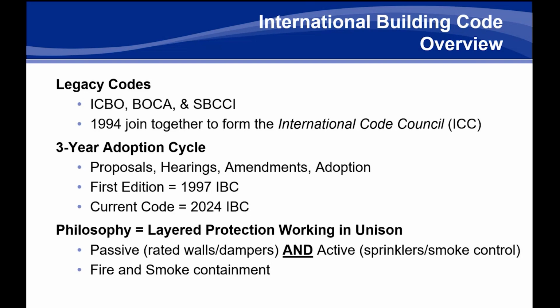The philosophy for that is actually a layered protection. So there's going to be a passive element and an active element. The passive element is typically you're going to be dampers or rated walls where the building design itself actually stops fire and smoke from spreading through the building. And then an active component would be either sprinklers to extinguish a fire or a smoke control system that can exhaust smoke out of the building or help control smoke spread with dampers and fans throughout the building. And that's really a layer protection of fire and smoke containment using multiple different technologies and multiple aspects to make sure if one potentially fails, there's something in place to protect both from loss of life and loss of property throughout that building.